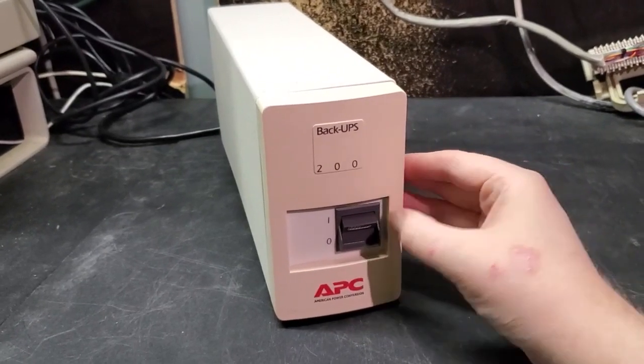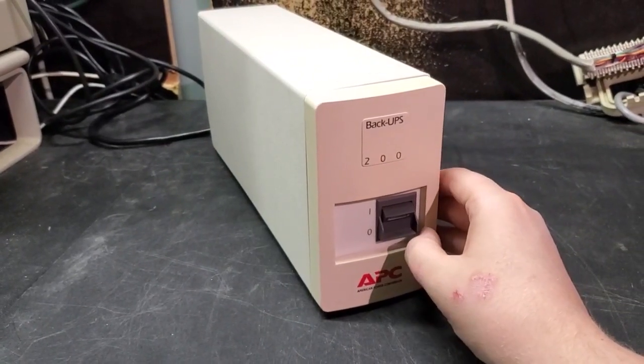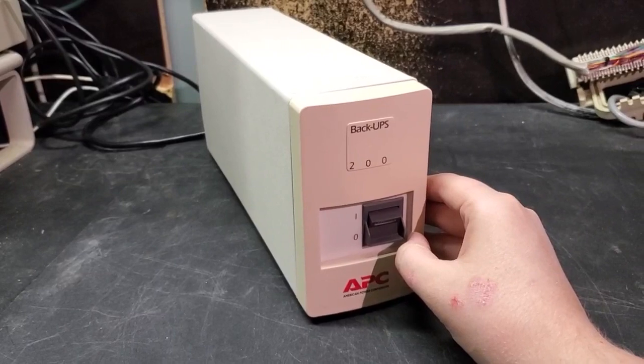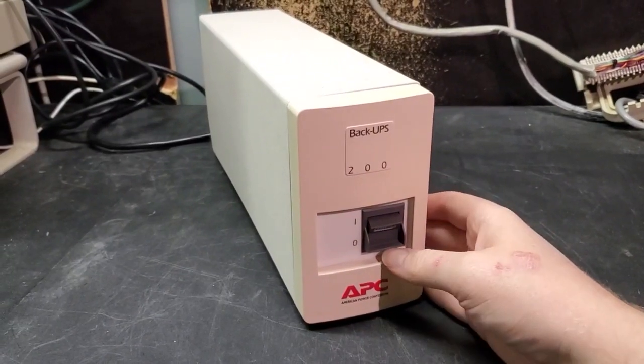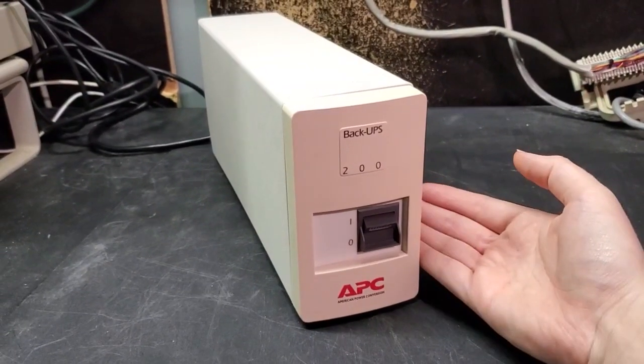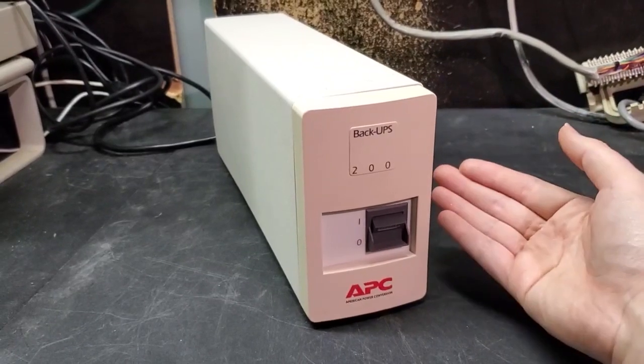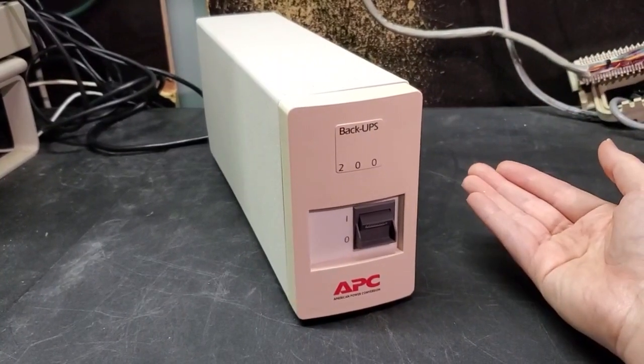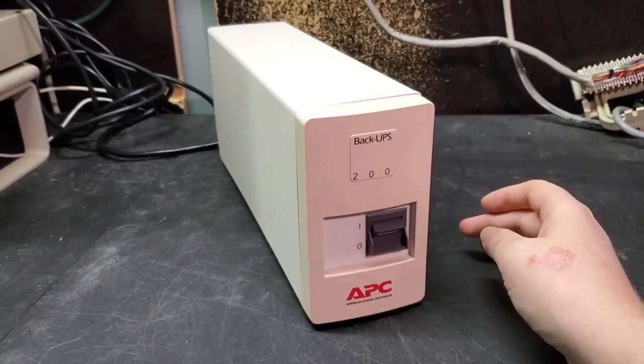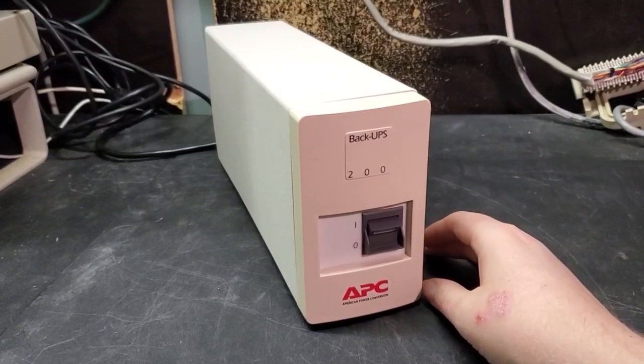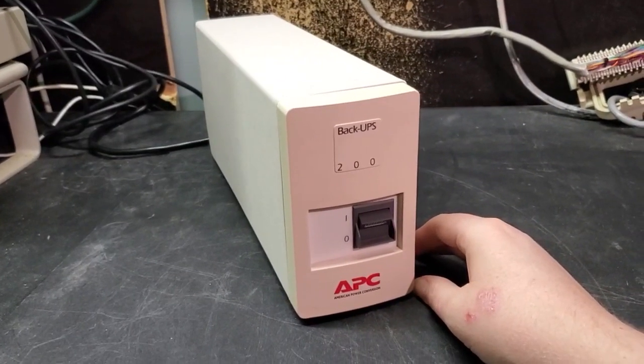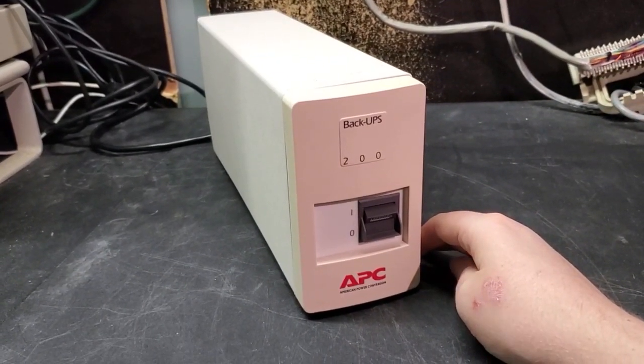That's because if this thing was running its full rated load for more than 5 minutes, there's a chance the inverter could overheat. I've subverted that little secondary safety feature by sticking in a higher capacity battery that'll allow this thing to run for more than 5 minutes at a full load. So I just have to be careful—I'll never run this thing at full load anyway, but it's something to watch out for.